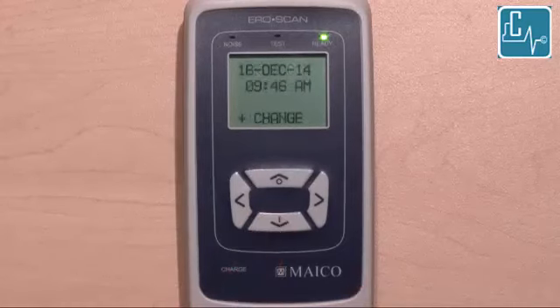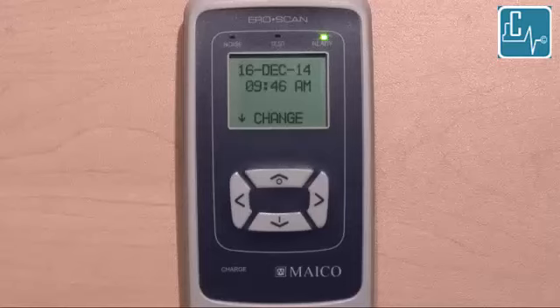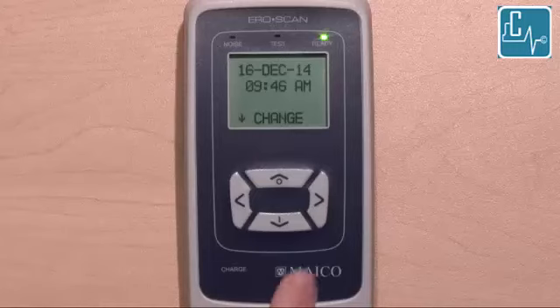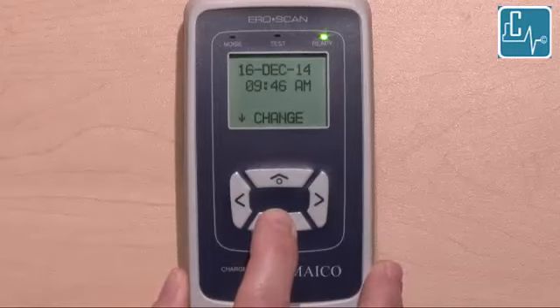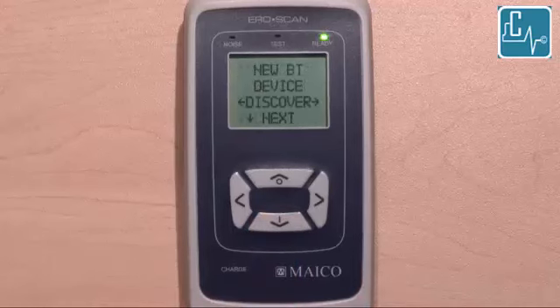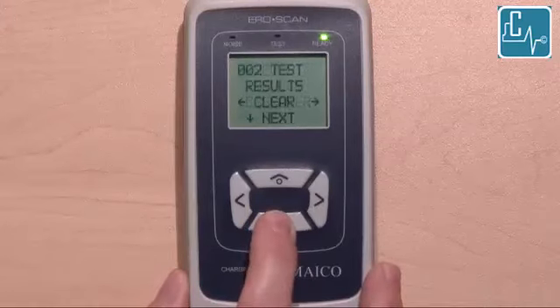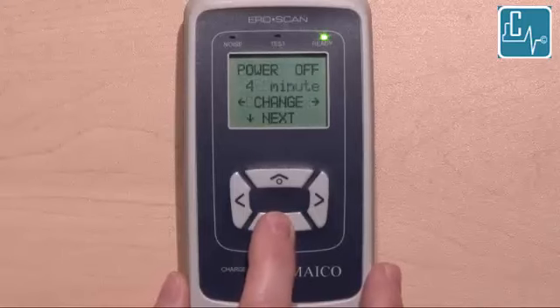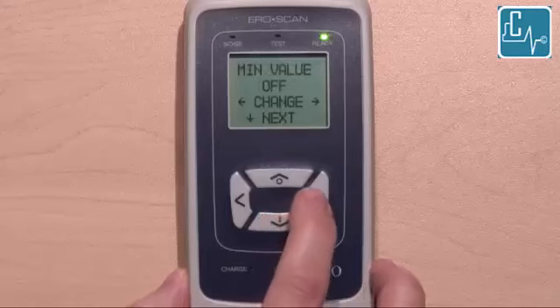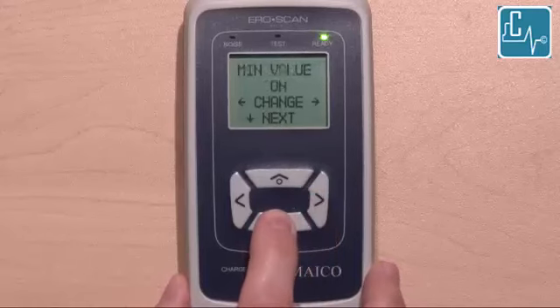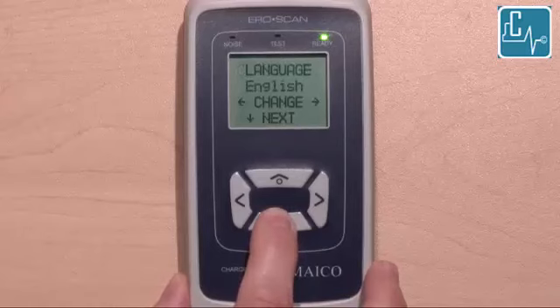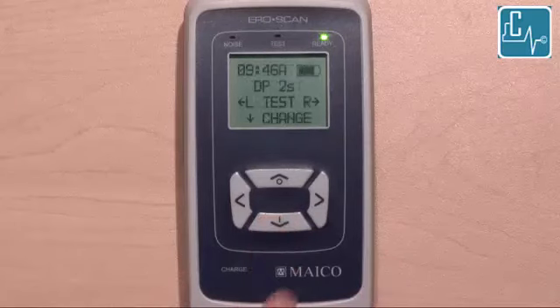You are now in the Date/Time menu, and Change is now displayed on the bottom of the screen. From here, you can also enter the next tier of setup items. To enter the next tier, press and hold the down arrow key for 3 seconds until the ready light at the top of the unit goes out. To make changes within the menu tier displayed, press the down arrow key to scroll through the items. Press the left or right arrow to make a change to a specific item. Arrow down through the menu to save changes. A flowchart schematic of the setup items is available in Appendix B of the Operation Manual. Full explanation of all setup items can also be found in the included Operation Manual.